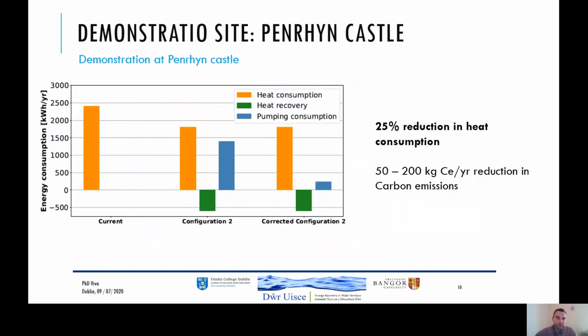After a month of operation, more or less, we saw a reduction of the heat consumption of the kitchen of about 25%, and an additional small part of electric consumption, which is related to the pump's consumption. This would save between 50 and 200 kilograms of carbon per year.